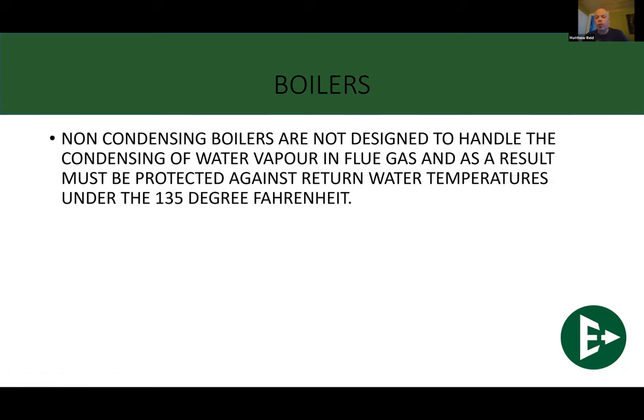Now, a non-condensing boiler, as I mentioned, is still only going to burn at, well, even a little bit less than that, actually, because they don't have the high efficiency burner types, but usually around 80% efficient, and that's out of the box, brand new. But these guys specifically must be protected against condensate, meaning that you make sure that your return temperature is well over that 135. Usually when we're talking about a non-condensing boiler, we have a supply temperature going out to the system at a minimum of 150 to 160 degrees.